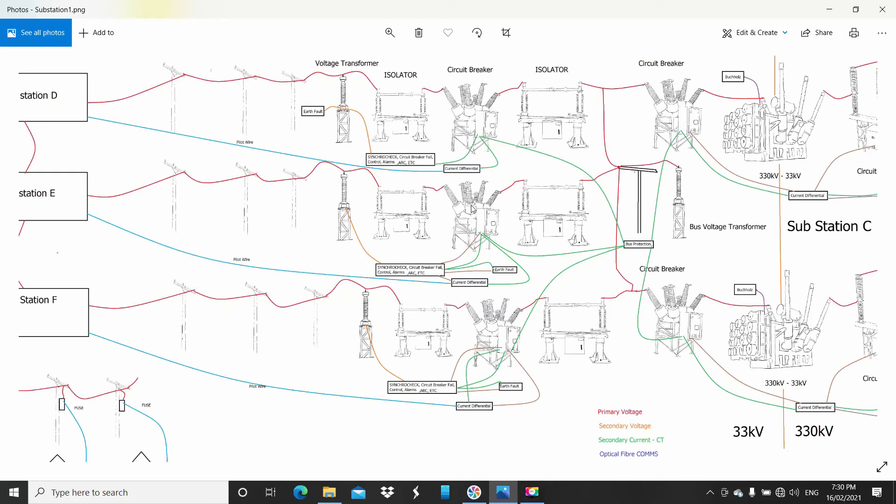The circuit breaker management relay would handle the auto-reclose. So if there's a fault, it would try and close again to see if it's cleared, close again see if it's cleared, until it locks itself out. We also have synchronization to make sure it's in its place, but we also have earth fault.